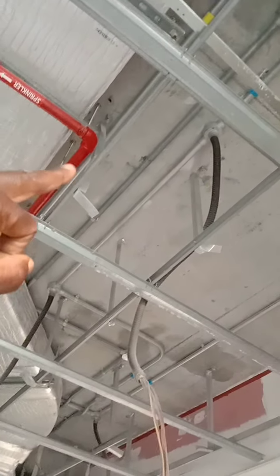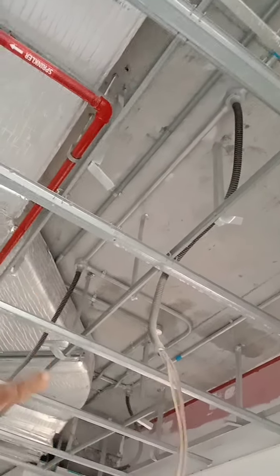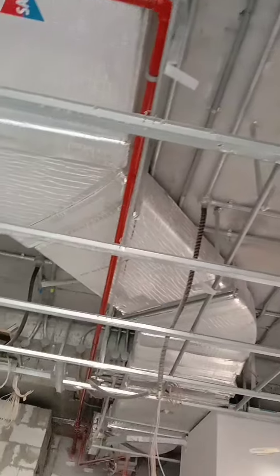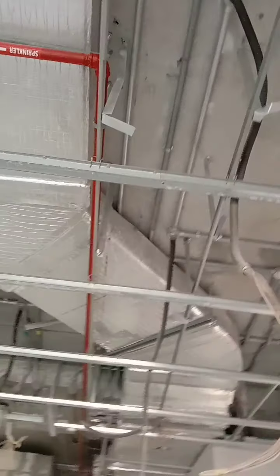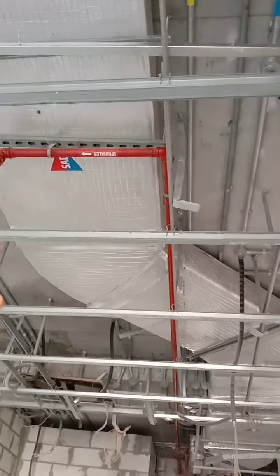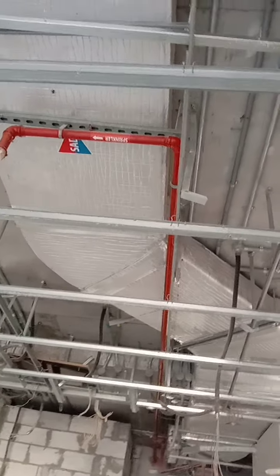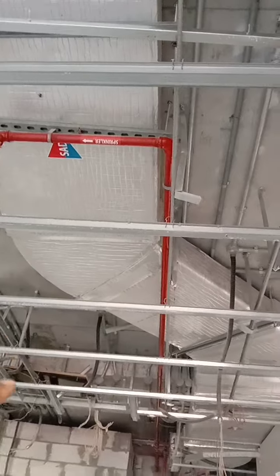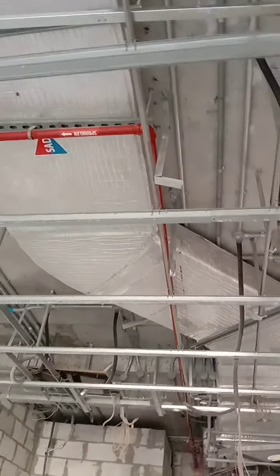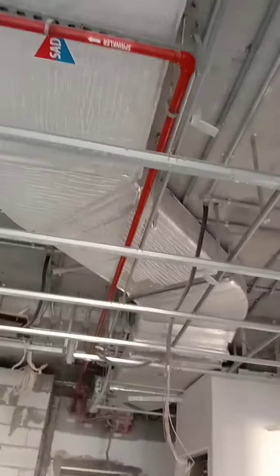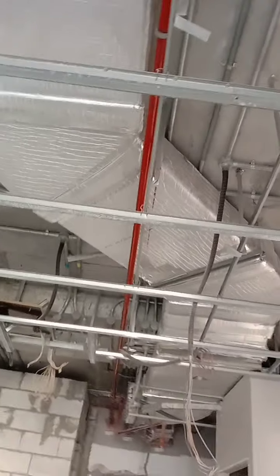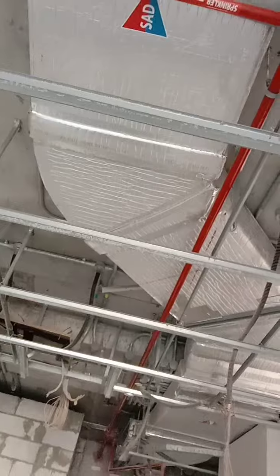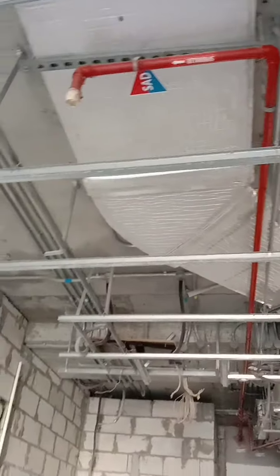As you can see, for the Copex or the flexible conduits which we've dropped, our wires are right inside. So everything has been done, and then we carry out continuity and megger test. We ensure that the first fix is done, the second fix which is wire pulling, as well as the continuity and megger test. We raise inspection and ensure that it is approved by the consultant before we can proceed with giving clearance for that particular location. Basically, for all the different services, we have to follow the same way.